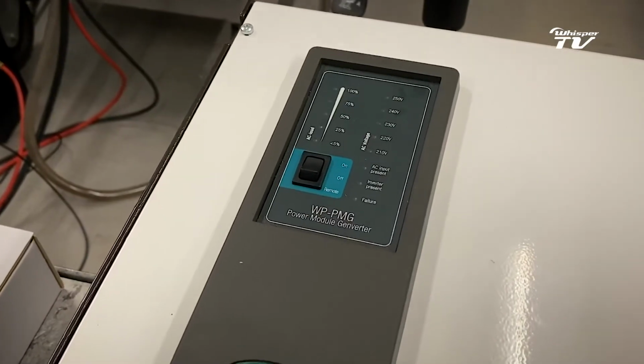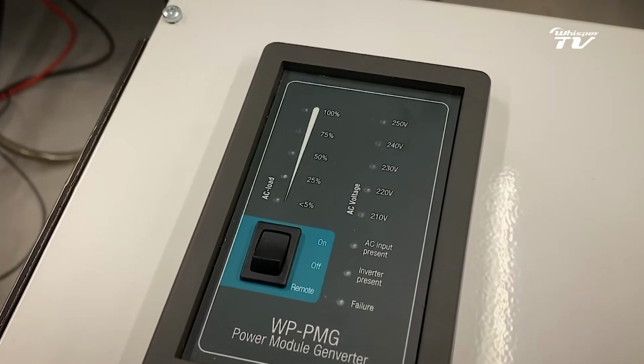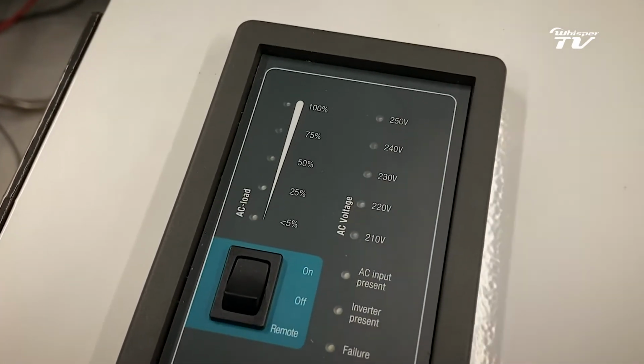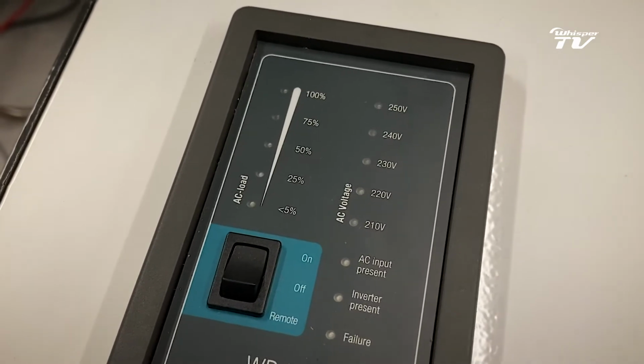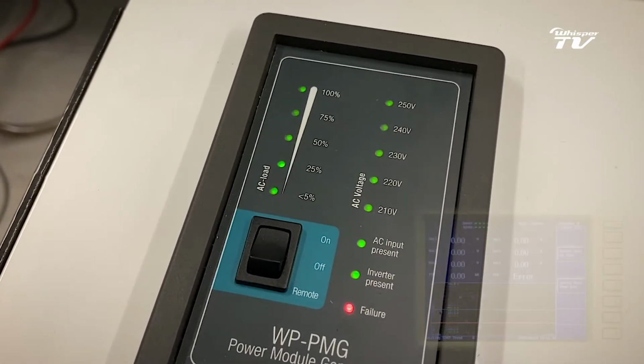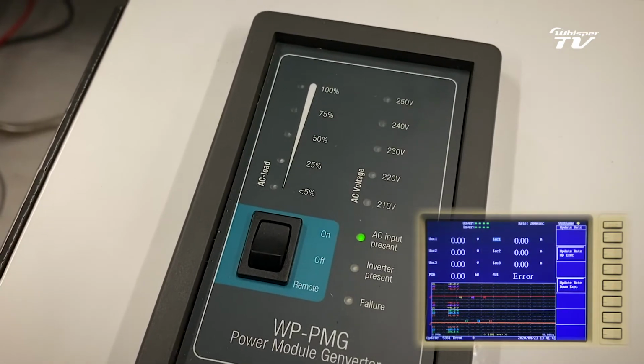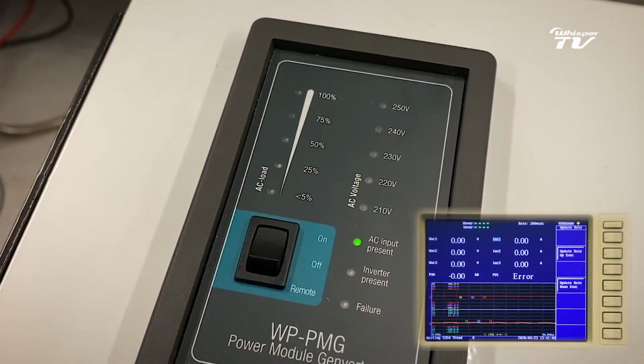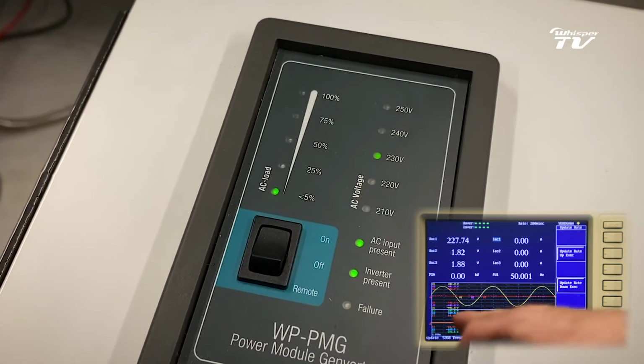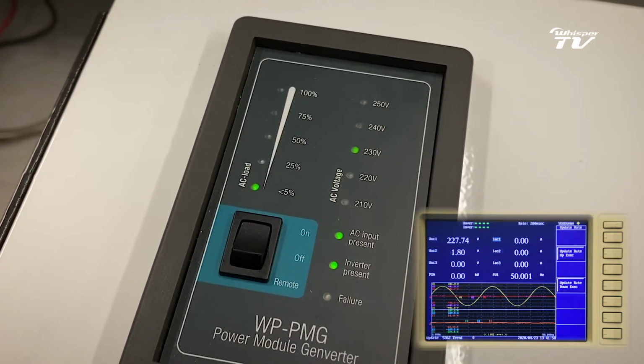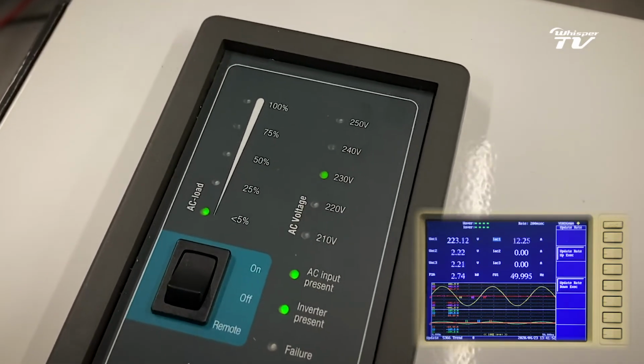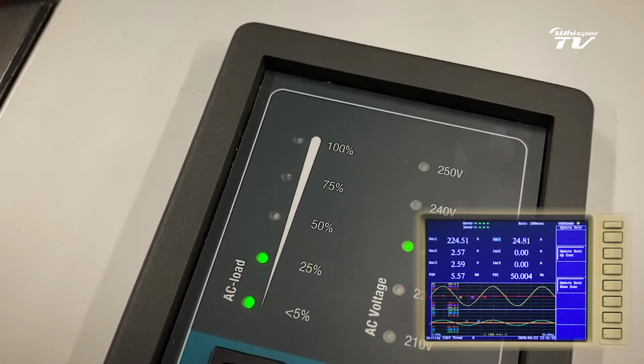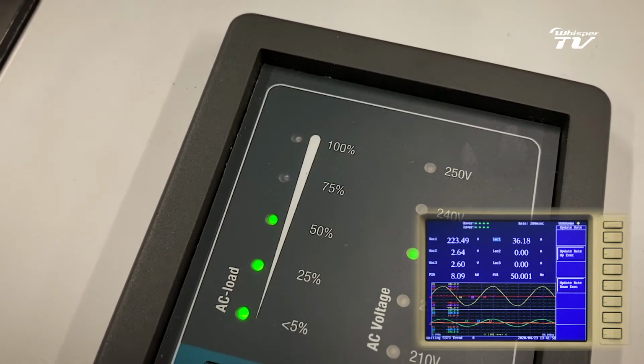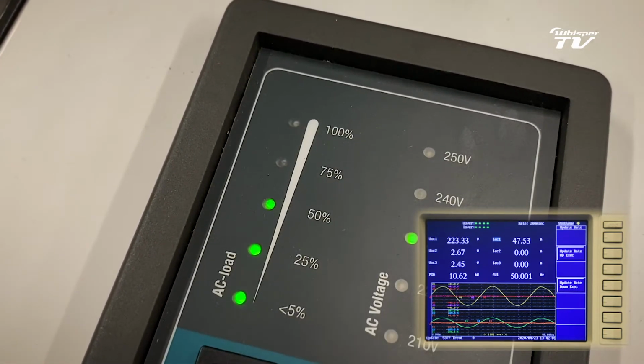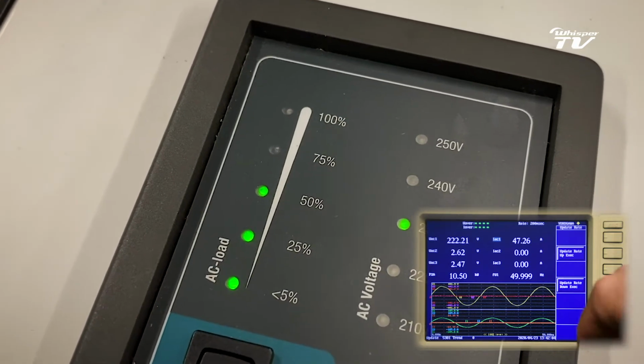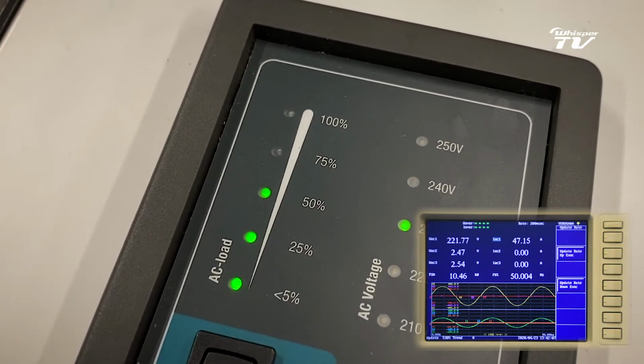We are going to start the generator, and then we can see on the screen and on the front of the inverter what's going to happen. Generator is running. It takes a while to get a sine wave, so the inverter kicks in, we see a pure sine wave, 227 volts. We switch on some loads. It's about 10.5 kilowatt, and that's still running fine and nice.